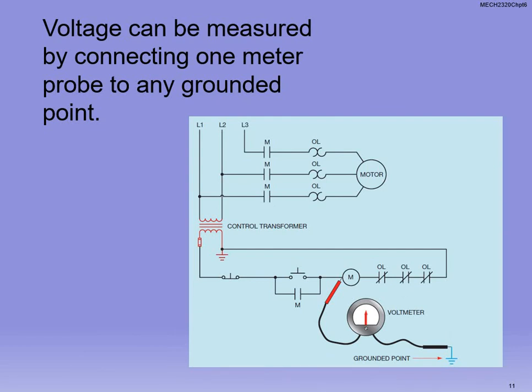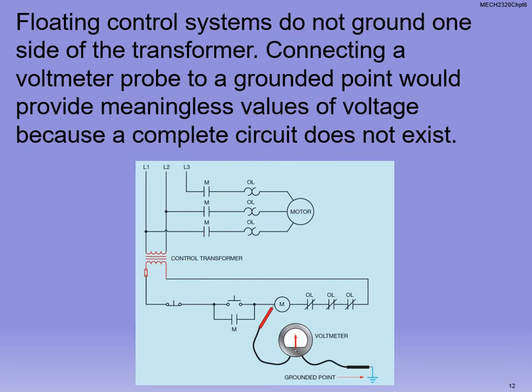Since it is tied to ground, that allows us to take readings and connect to anywhere. As long as the transformer is grounded on one side, we can connect to a grounded point anywhere else and get an accurate voltage reading, okay? To make sure, if we need 480 volts across the line there, that we're reading 480 volts as required. But common industry practice doesn't always ground the control transformer. So notice in the schematic here, it's not grounded. So what this does for us though is this is a meaningless voltage because it's not in the same system. So that grounded point, since that control transformer doesn't go to the same ground as what you're using for reference here, okay, our voltage, we call them like ghost readings.